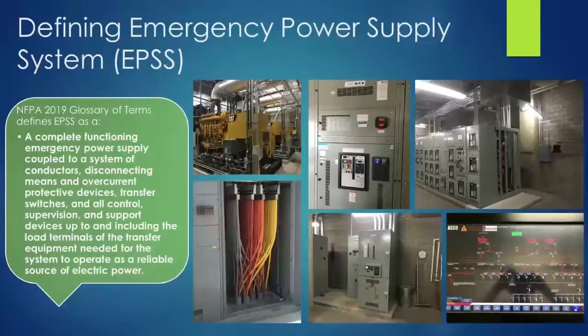So why commission the healthcare? Why do we do this? There are applicable codes: your AIA guidelines, NFPA 99, NFPA 101, NFPA 110. All of those set out how our emergency power supply systems should operate, and they define what it should be. Well, how do we verify that the system actually operates as code would tell us it should? The only way that we can do that is by testing. So, verification by testing. The applicable codes say that we need to test.